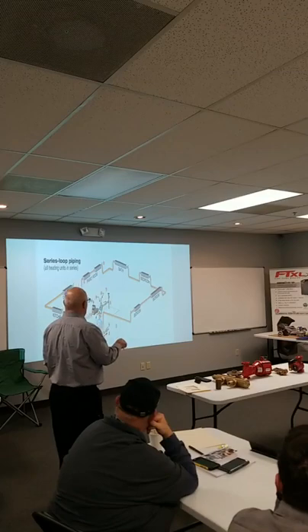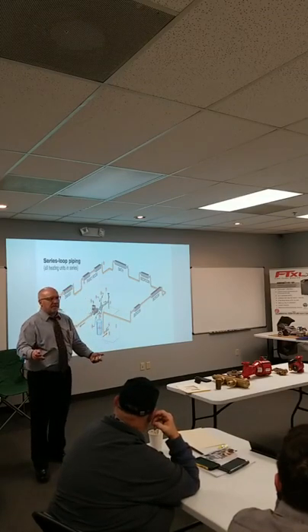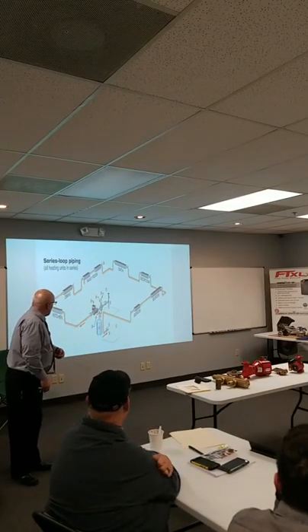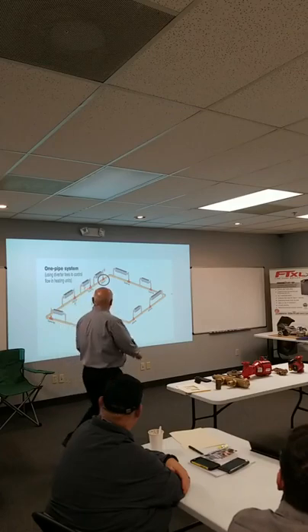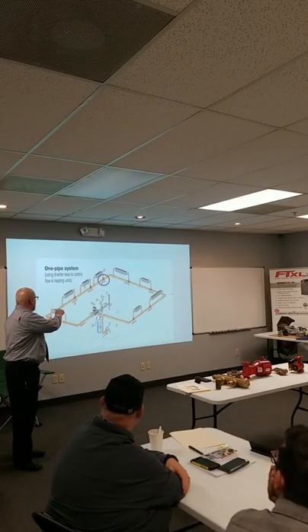If I put a valve in here and I shut it off, I shut the flow off to the whole system, right? So the old guys were pretty smart. What they did was they designed a monoflow tee, one pipe tee, exactly. So now they have a main that flows through here back to the boiler.